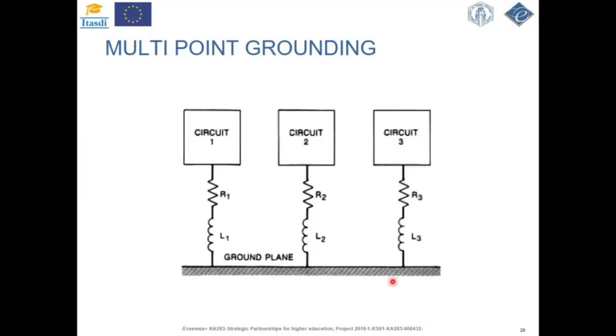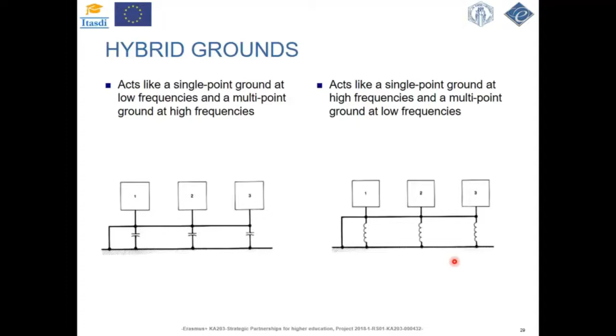On this slide, we can see a hybrid ground. On the left-hand side, we can see a circuit which acts like a single point ground at low frequencies and as a multi-point ground at high frequencies. Let's consider, for example, that we have a DC component. For a DC component, the impedance of these capacitors is very high, theoretically infinite. So that means that we have an open circuit here, and we have a single point serial connection. And if we have a high frequency, then the impedance of the capacitor is nearly zero, so we have a multi-point connection. The circuit on the right-hand side is more or less similar, but this circuit acts like a single point ground at high frequencies and a multi-point ground at low frequencies.